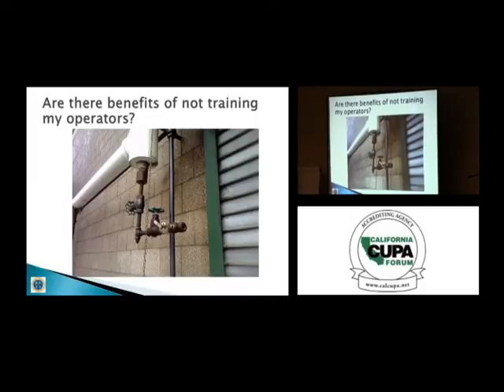What they're doing here is removing oil from that part of the system. And so they got a hand valve and a collection point and another hand valve. Lee, can you tell if that is a self-closing valve there? I'm thinking it's not. Okay. In fact, that might even be associated with another line. Point is, does the operator know what this does, how to do it, what the personal protective equipment is, and is there a better way?